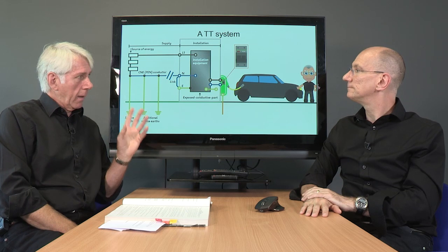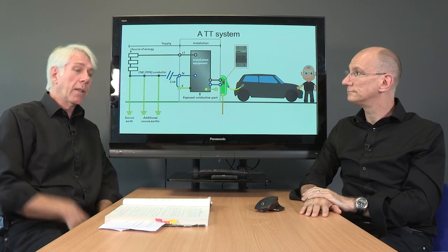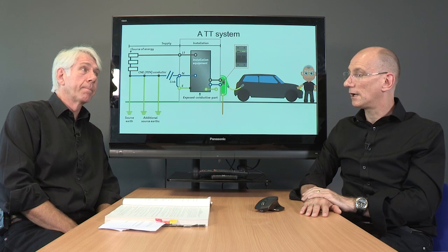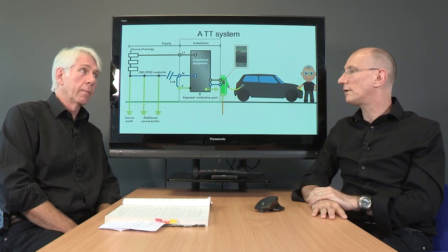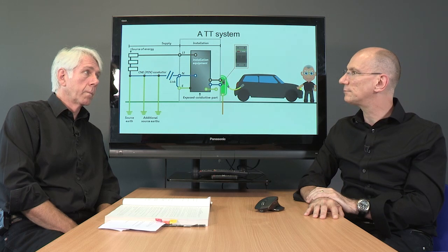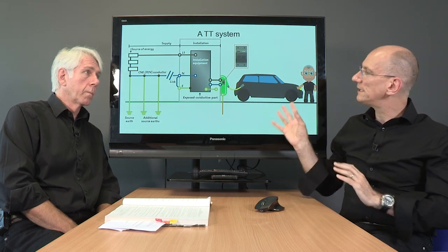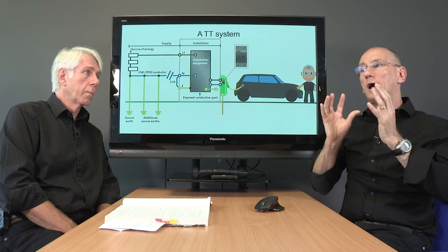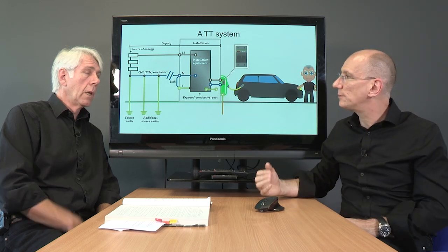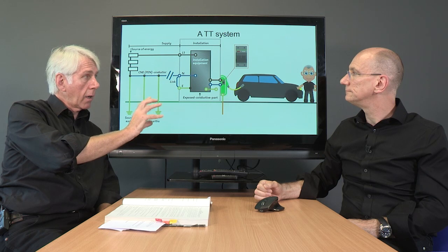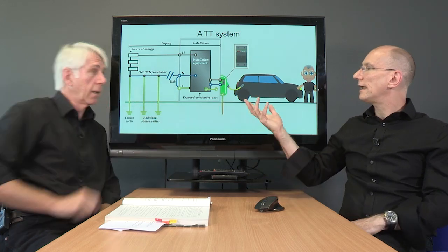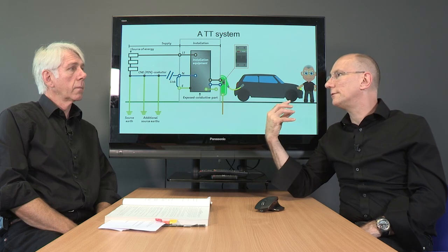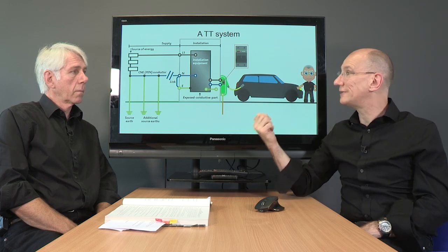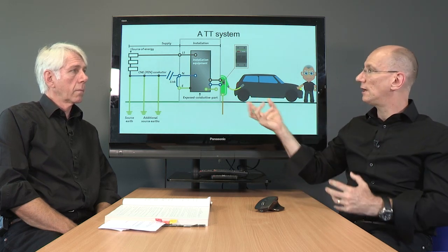Call me an old cynic, Gary, but I'd say that this particular issue hasn't been accurately nailed yet, has it? No. We need work on this, don't we? This is not clear. No, I'm sure everything in life is work in progress and things are being done to address this. But this is an option seen by many to help alleviate a potential problem. So you think that most of the installations going in at the moment are most likely opting for this TT arrangement? Yes, I think listening to and reading options, a lot of DNOs, a lot of suppliers have gone down the TT route because they don't want to have that issue of a risk of losing the neutral and having a fatality on their hands.